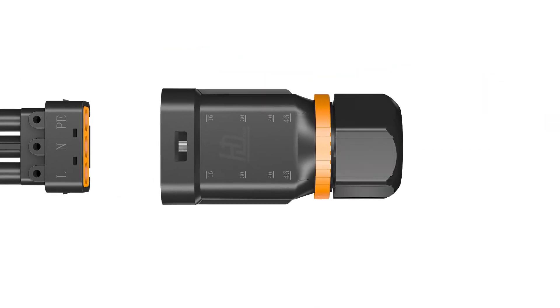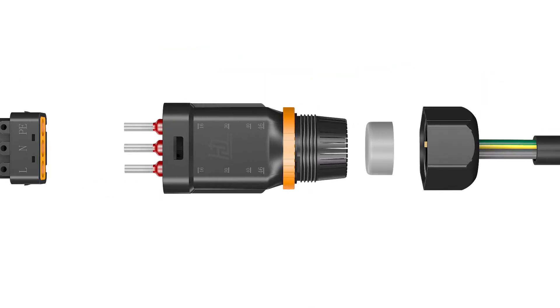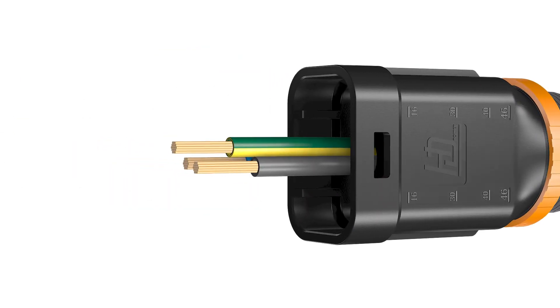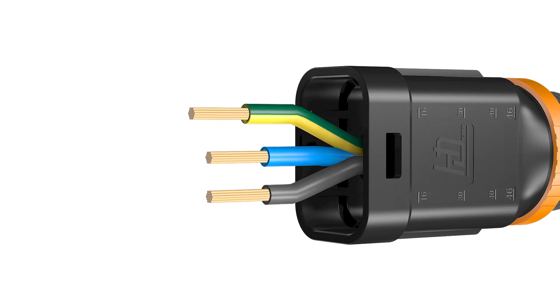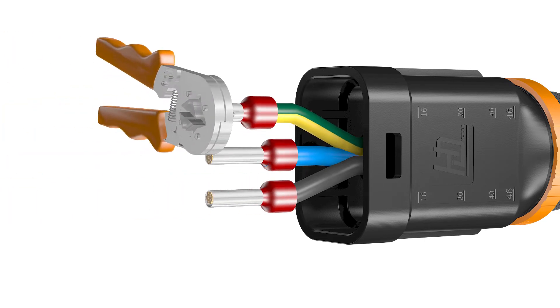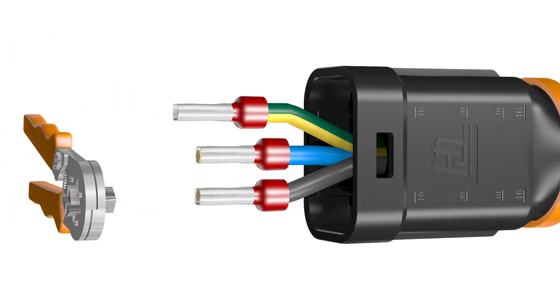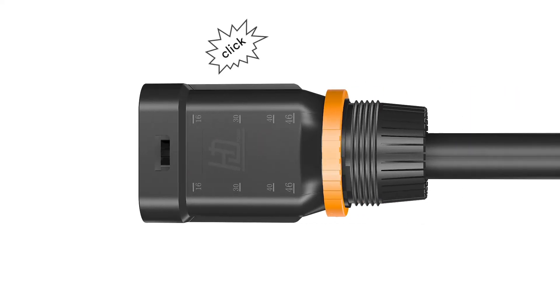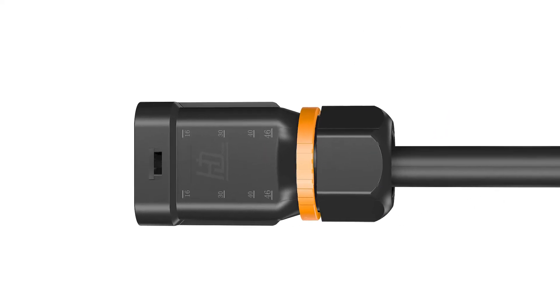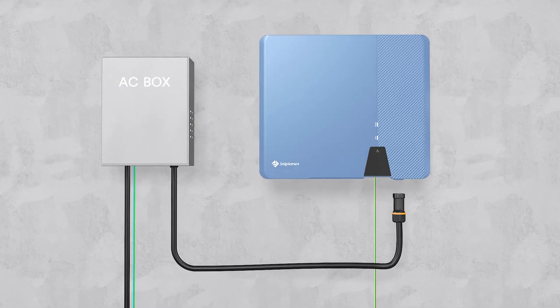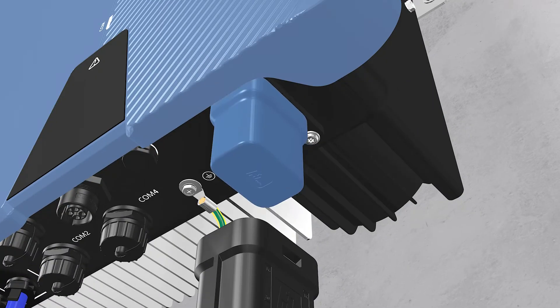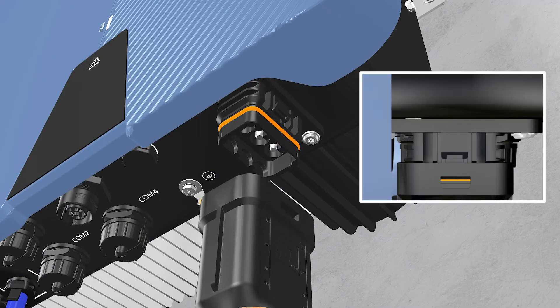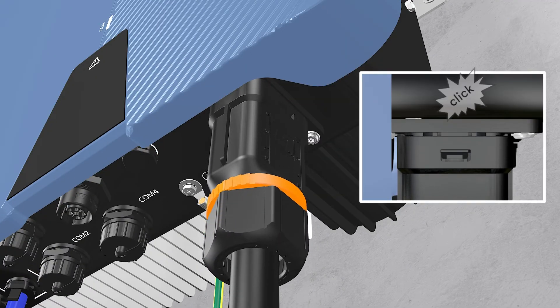Loosen the swivel nut of AC connector. Insert the crimped conductors into corresponding terminals and tighten screws with the accompanied Allen key. Insert the adapter to the socket element, stuff the seal ring into the adapter and tighten the swivel nut.